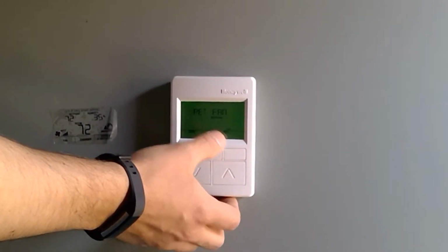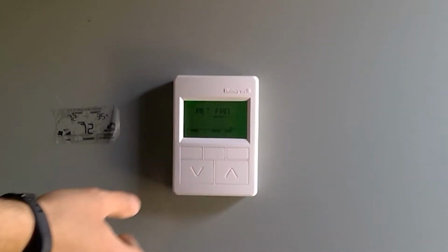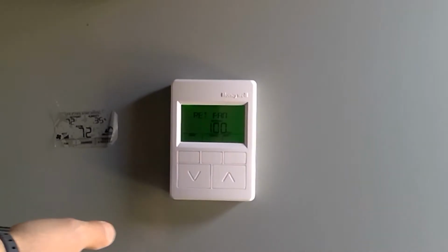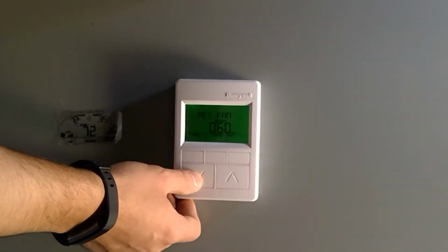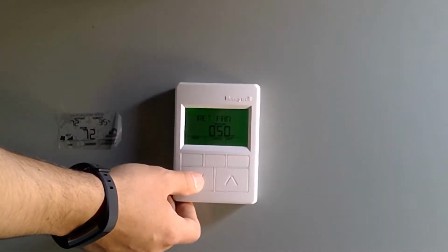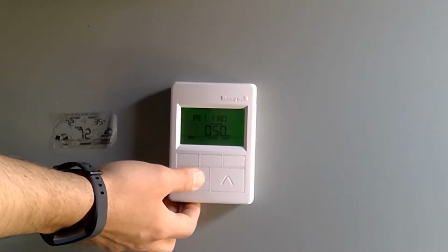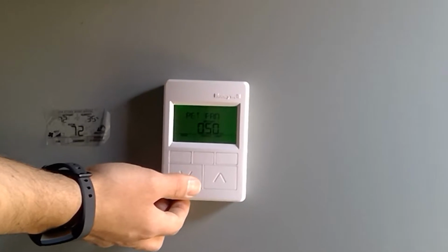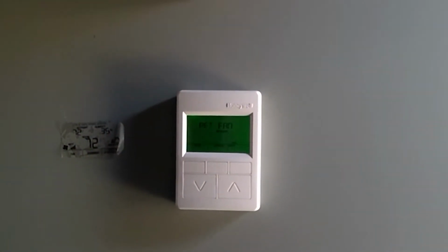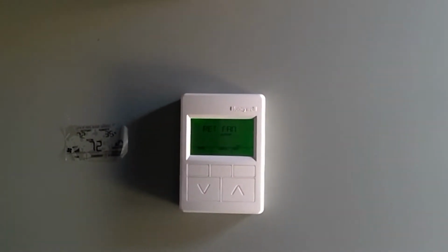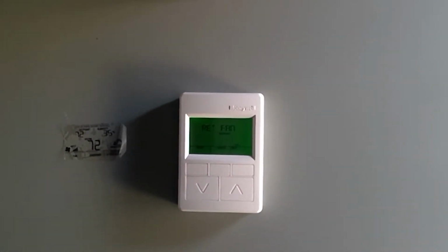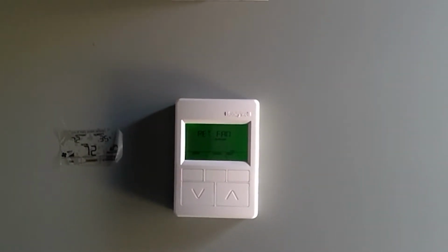So return fan, this is your static pressure set point, set for 1 inch right now. Okay. So we're probably going to want to lower that because this was only maintaining 0.5. So maybe 0.5. That'll modulate the vortex damper. So when it went closer to neutral, closer to 0.4, is when it should have started closing down, right?